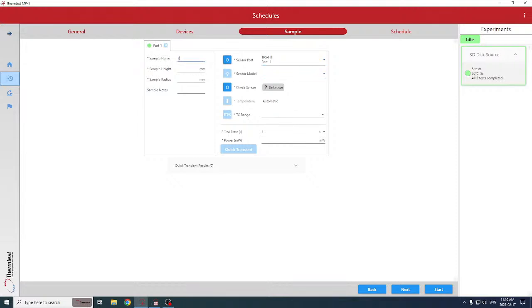Here we can name our sample. So this is stainless steel 304. Our sample height is 20 millimeters. I've previously measured this. Our radius is 20 millimeters. We have an auto suggestion of sensor size, ideally suited because of the dimensions you enter. So it suggests 33171. Had I not known what sensor to use, I could have done this step first, then set the sensor up. The sensor we used was 33171, or 6.4 millimeters radius. We're going to check the resistance. That just ensures that we have electrical connection with the sensor, or if we have the wrong sensor connected, it'll give us a red warning saying something is wrong.